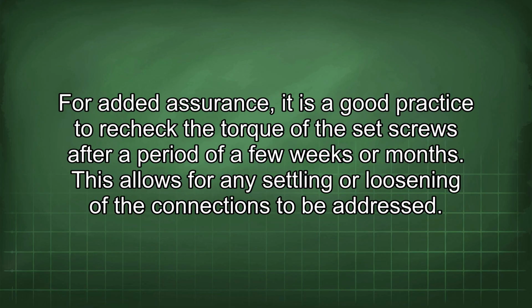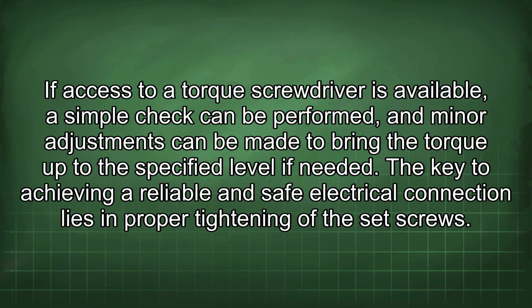For added assurance, it is a good practice to recheck the torque of the set screws after a period of a few weeks or months. This allows for any settling or loosening of the connections to be addressed. If access to a torque screwdriver is available, a simple check can be performed, and minor adjustments can be made to bring the torque up to the specified level if needed.